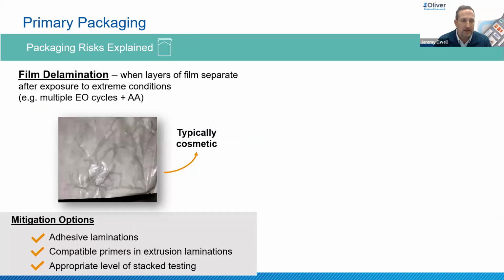So starting with film delamination, this is a phenomenon when layers of film separate after exposure to extreme conditions. We have written here EO cycles, but also any type of gas sterilization, combined typically with accelerated aging and maybe other stack testing afterwards. And typically it's cosmetic. If you do testing on the sterile barrier, you're not always going to see a breach of the sterile barrier, really just an eyesore. The film's separated from itself, and it looks like it's probably weaker, but it could pass further testing. So we do call it cosmetic to begin with, until that further testing is performed.